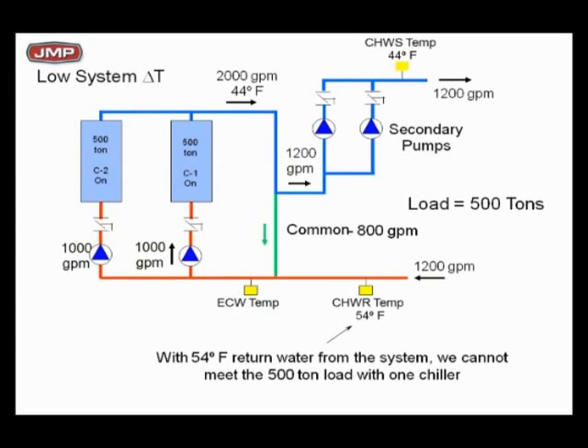Design was 12 degree delta T on the load side, but you're going out at 44, coming back at 54, I only got 10 degrees. So now we got a problem. We have to run both chillers to give you 500 tons. Bottom line is, what's going to happen if you get a total 1,000-ton load? You can't get the BTUs out. So now you got 50-degree return water to each chiller, and each chiller is going to give you 50%. Look at the wasted energy because of this low system delta T. Nothing to do with primary secondary. This is because you're not giving me 56-degree water back.